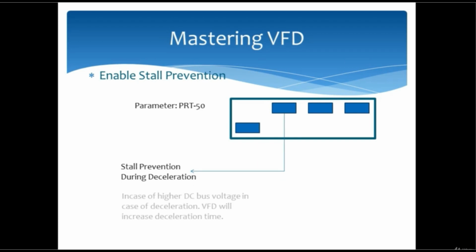As soon as the DC voltage gets higher, the VFD increases the deceleration time. So instead of stopping in 3 seconds, for example, it might stop in 5 seconds or even longer, which all depends on the load condition.